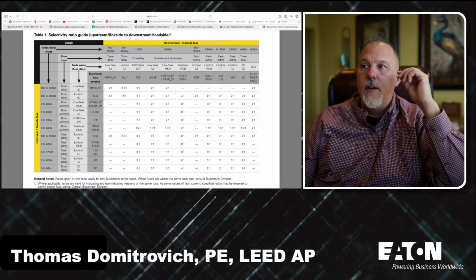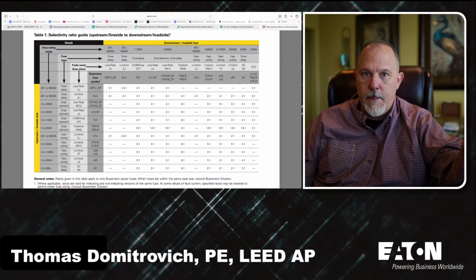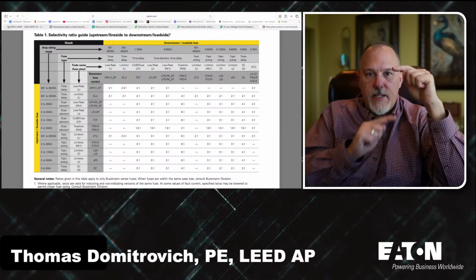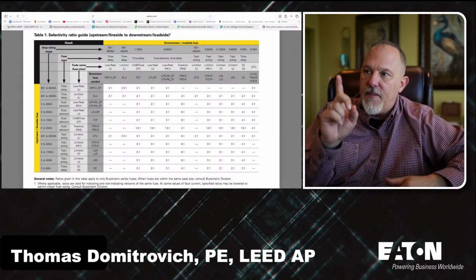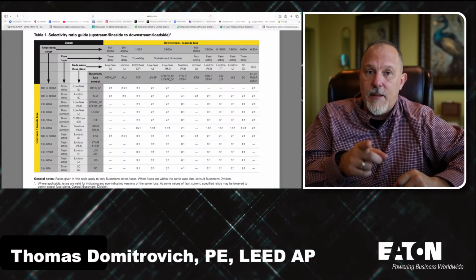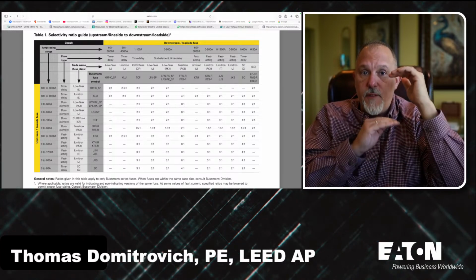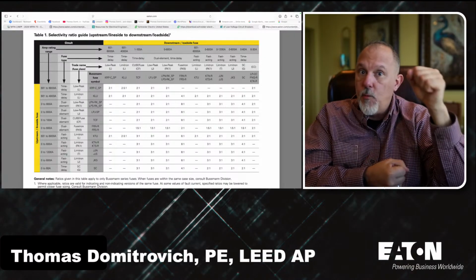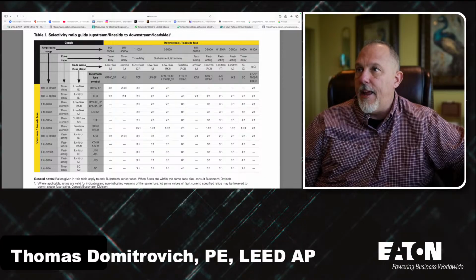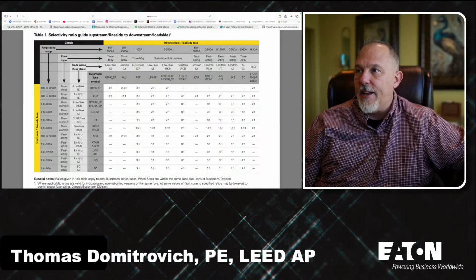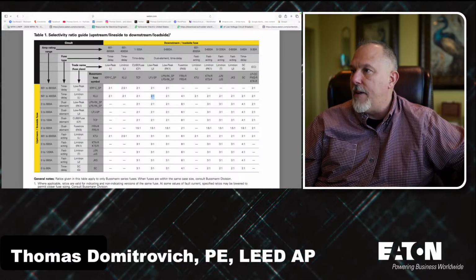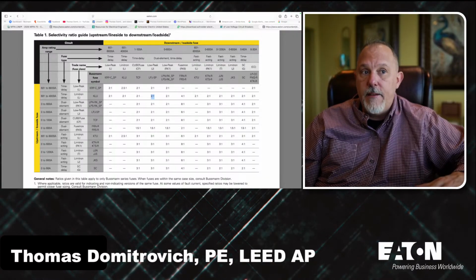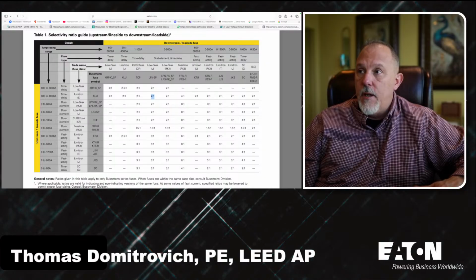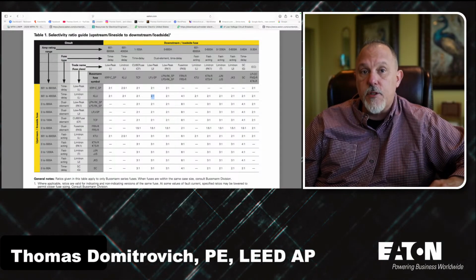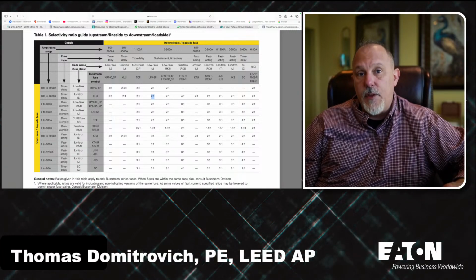So you've got to always go back to the manufacturer's tables to understand, when I have two devices in series with each other, how much current can I pass through there? If I maintain the ratios, that's telling me I can put up to 200,000 amps through both fuses. The downstream will open and the upstream will not, right? So if I had an LPJ 30 downstream of a KLU 60, and I put 200,000 amps through both of those fuses, that LPJ downstream 30 amp fuse is going to trip first before that 60 amp fuse upstream. All right, so hopefully that answers that one.